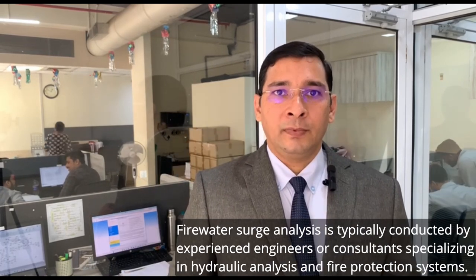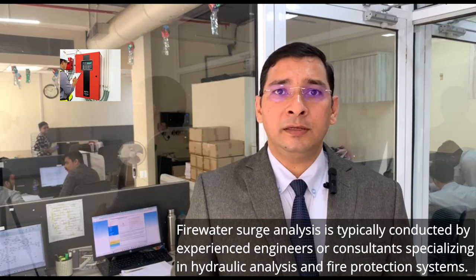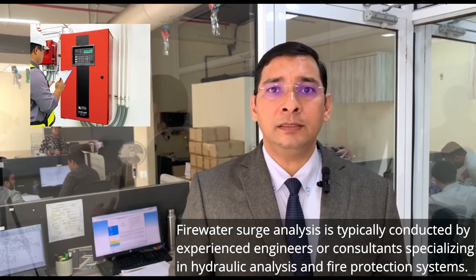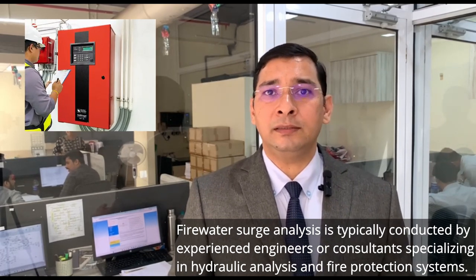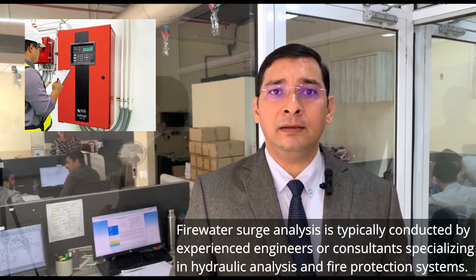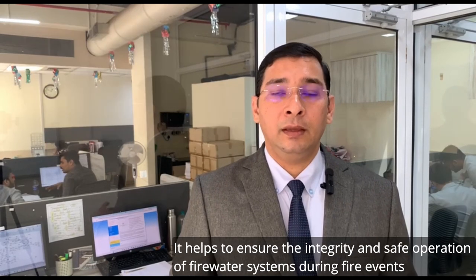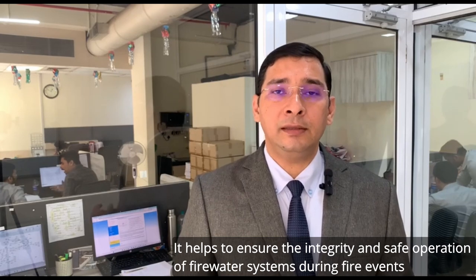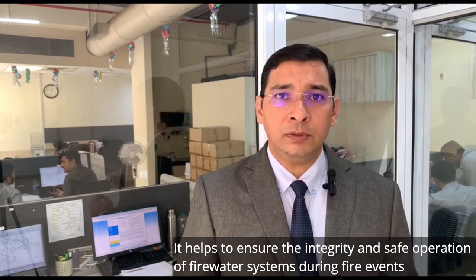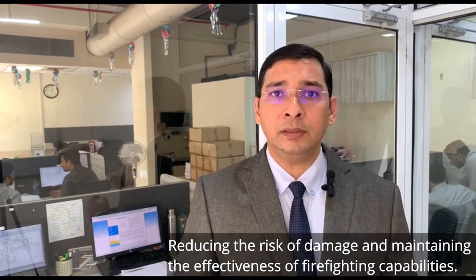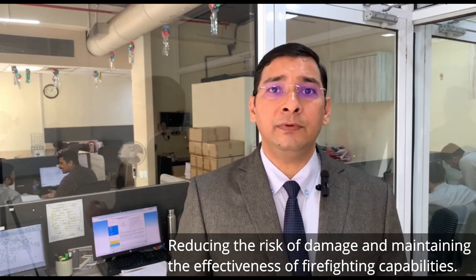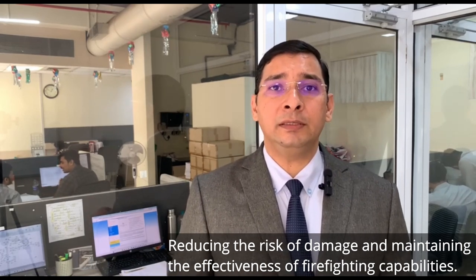of the analysis. Firewater surge analysis is typically conducted by experienced engineers or consultants specialized in hydraulic analysis and fire protection systems. It helps to ensure the integrity and safe operation of the firewater system during fire events, reducing the risk of damage and maintaining the effectiveness of firefighting capabilities.